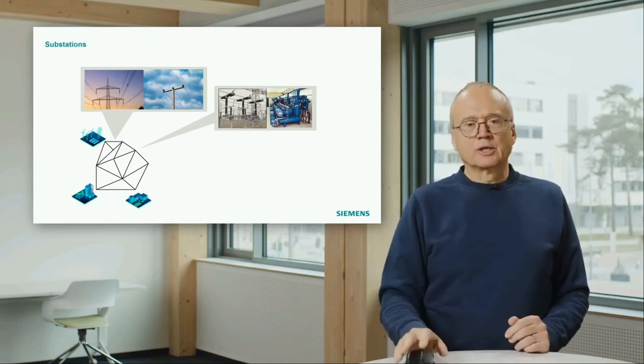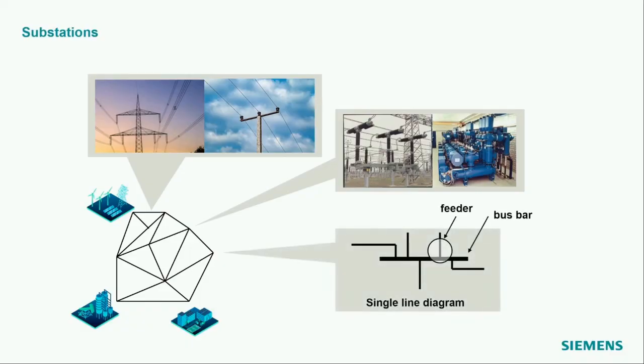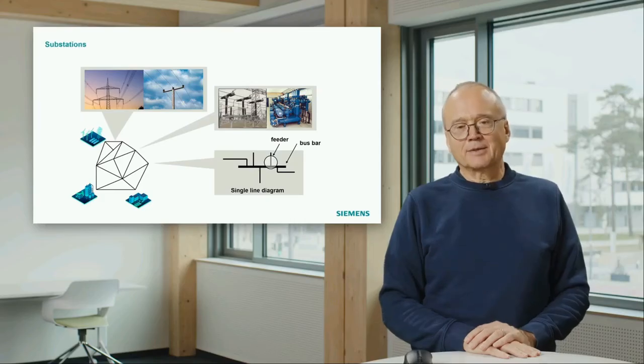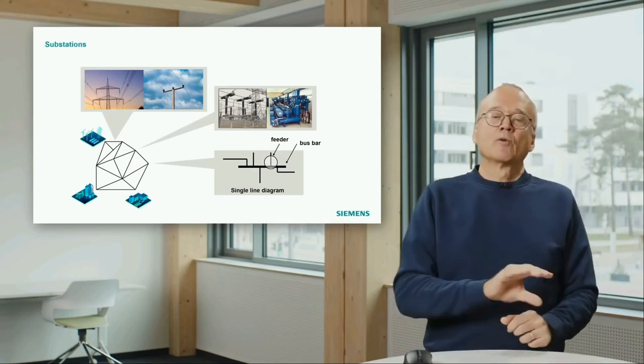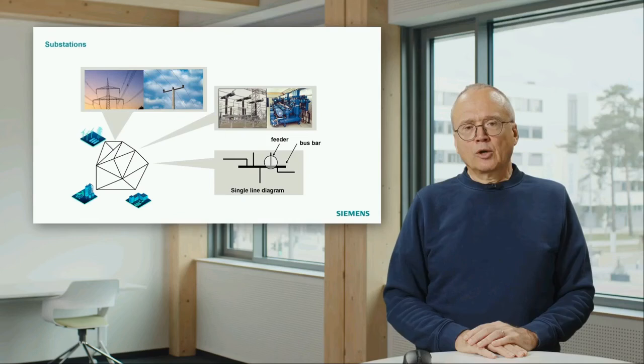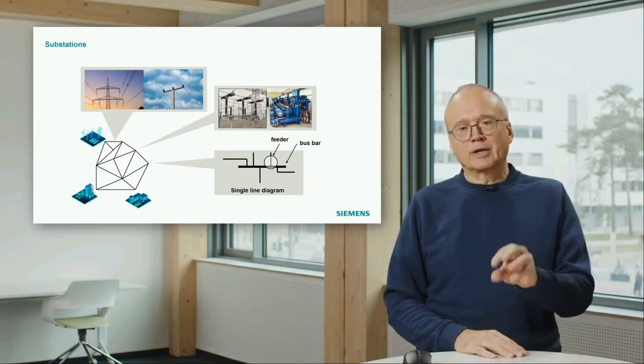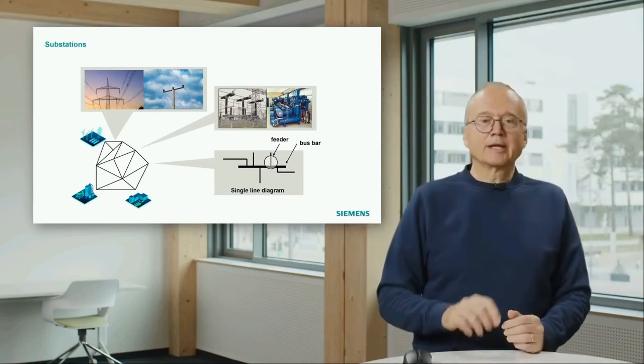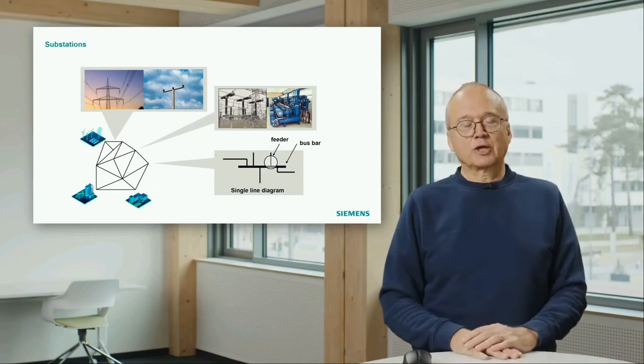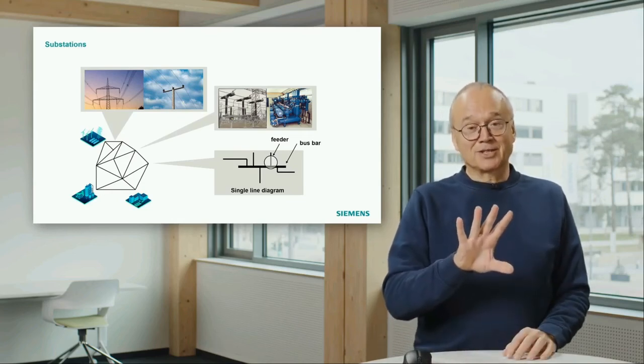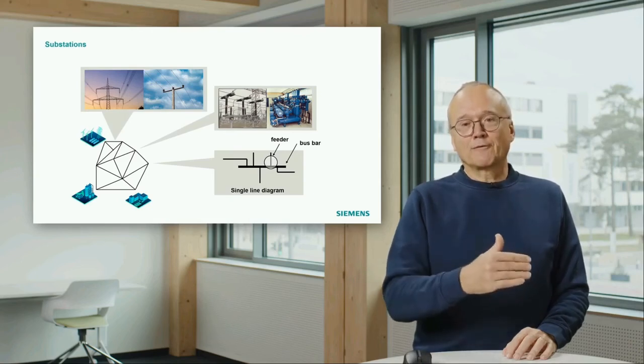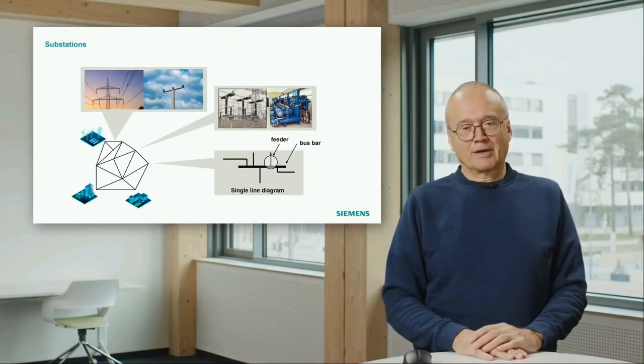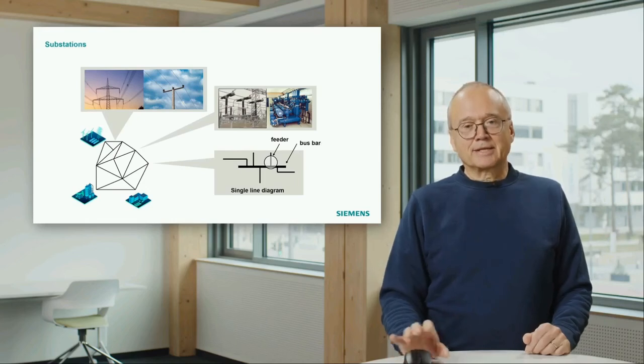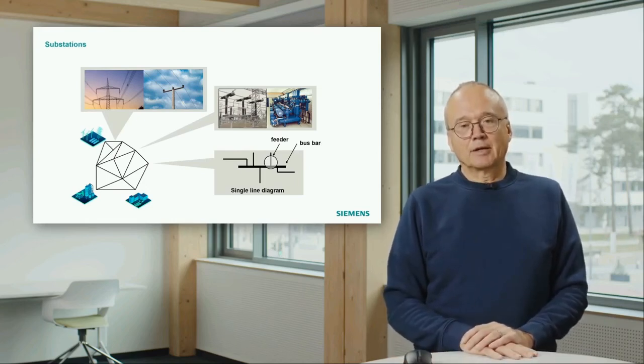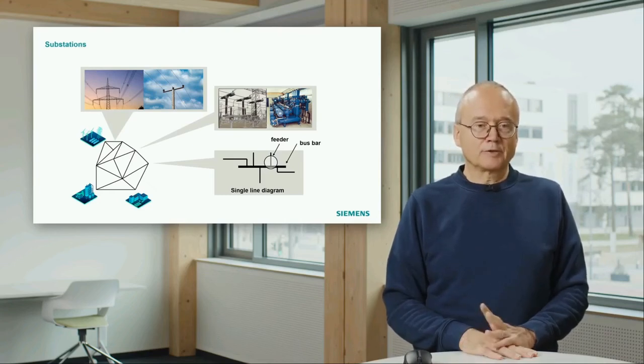And if we now zoom out a little bit more, it looks like this. That means we have not one point where all the lines come together. We have a so-called busbar, and all the outgoing feeders from this substation are connected to a busbar, and at the beginning of every feeder, you have such a circuit breaker and a protection relay installed. Always remember, this is a single line diagram. That means in reality, you have 3 bus bars available there. These slides with the circuit breakers are pictures for a transmission voltage level.